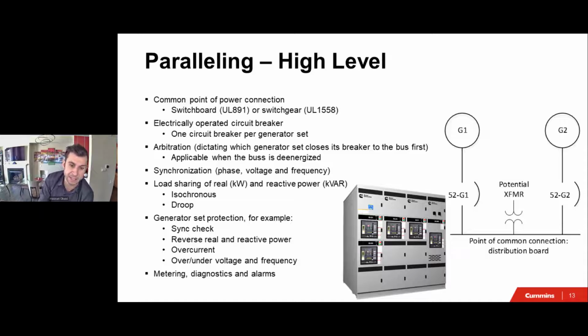And this is why we need to sense, this is why I have the potential transformer in here. If it's a high voltage, or it could be some generator controls, they can sense up to 600 volts directly off the bus. Once you're synchronized and the magnetic flux is coupled between the alternators, they're running like one machine now, so we don't have to worry about that.